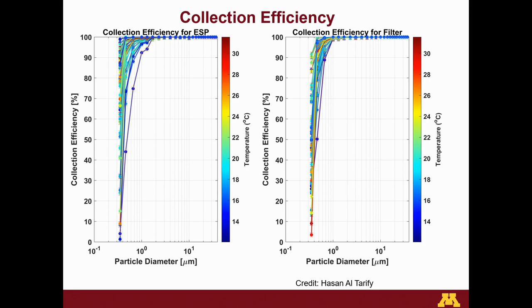Collection efficiency is a function of temperature, and so Hassan was able to look at those efficiencies by ambient temperature, etc. These values down here on the very low bottom, fractional efficiency on a MERV 14 at 0.3 micron would typically be somewhere down here. This is just very, very low particle counts, in which it's hard to get a ratio of a numerator and denominator of any exactitude.